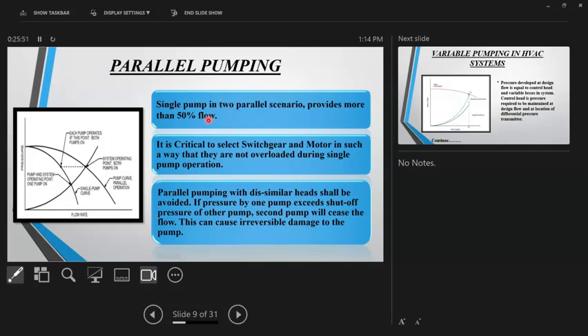Let's say there are two working pumps, each of 100 gallons per minute, and the system requirement is 200 GPM. So I selected two working pumps of 100 GPM. When both of them run, obviously no problem, they would produce 200 GPM. Now, if you switch off one pump and run only one pump, we think that the pump will give only 100 GPM. But that's not what happens. The running pump may give you 150, 160, depending upon the shape of its curve. So one running pump will actually give more than its rated capacity.